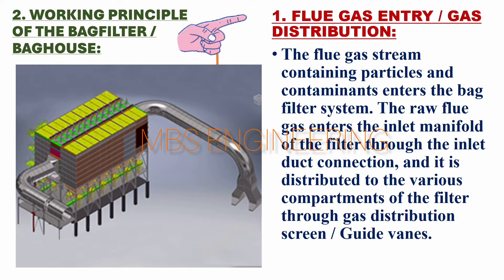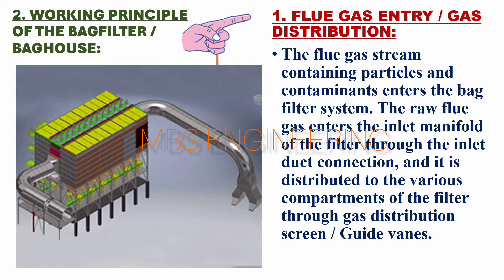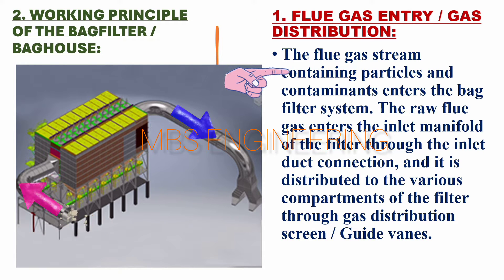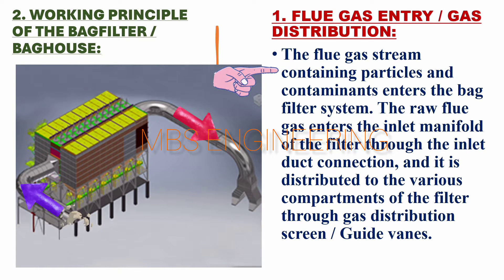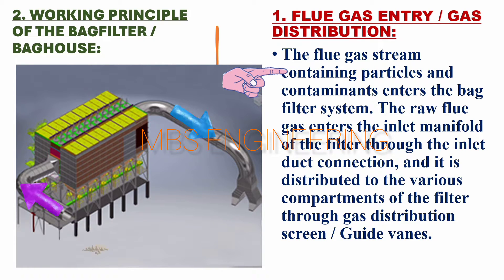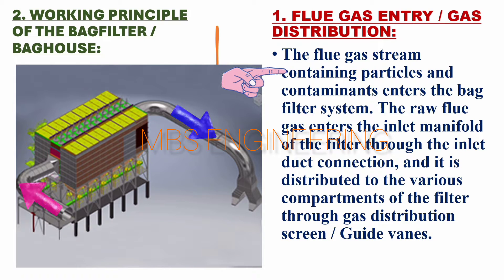Step 1 — Flue Gas Entry: The flue gas stream containing particles and contaminants enters the bag filter system. The raw flue gas enters the inlet manifold of the filter through the inlet duct connection, and it is distributed to the various compartments of the filter through a gas distribution screen and guide vanes.